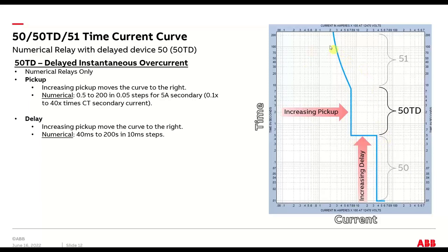So you can combine them. As a composite, you have your 51 time overcurrent plus your 50 time delay, and then your instantaneous, which is 50. This would be for your bolted faults. Time delay would be for high impedance faults or where you want the breaker to hold in to allow for coordination. And then your time delayed overload and high impedance protection. So that's sort of an innovation that came out with the advance in numerical relays.